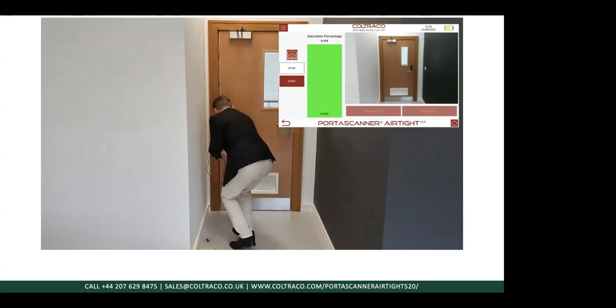Now, Angus uses the wand to look for leaks in the door's seal. He is looking for spikes in the signal indicator and will mark a leak when he spots it by touching on the relevant part of the photograph. As you can see, the ultrasound can penetrate at this particular part of the door seal. Angus looks for the spot where the red bar reaches its maximum and touches the corresponding part of the photograph on the screen. Angus now positions the wand as close to the point of maximum signal as he can. He presses the measure button and holds the wand as still as possible while the receiver captures data about the leak. Once the measurement is complete, Angus continues to scan the door, marking and measuring any further leaks that he finds. In this case, Angus has found 2 leaks.